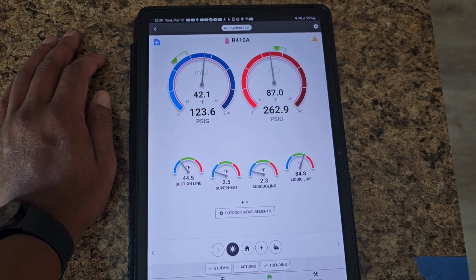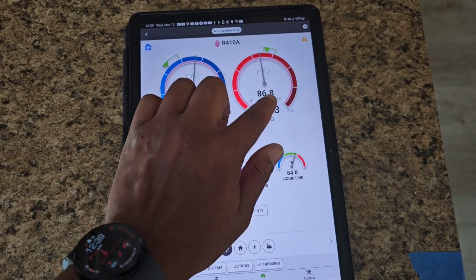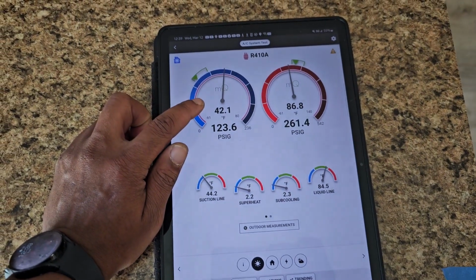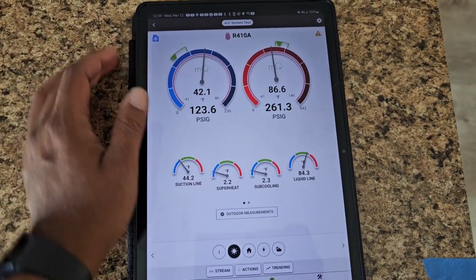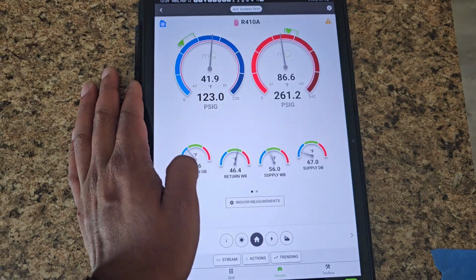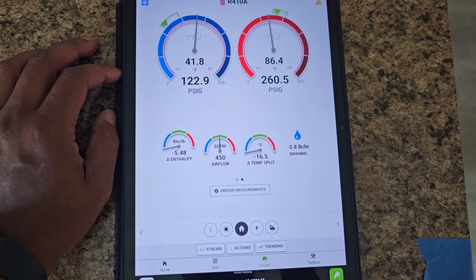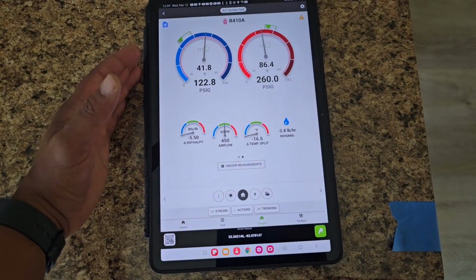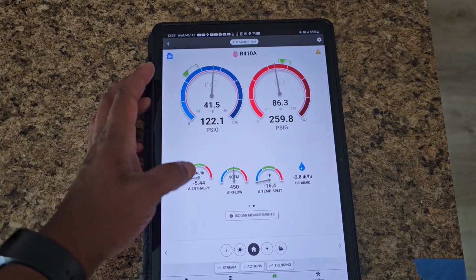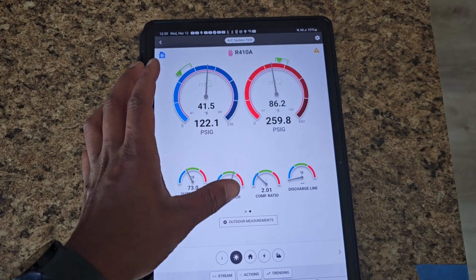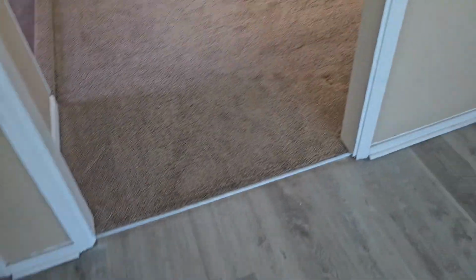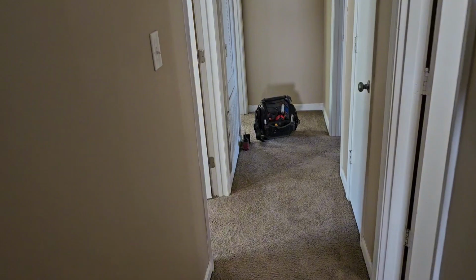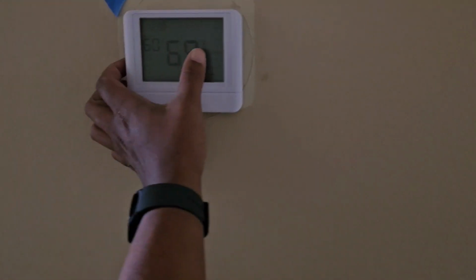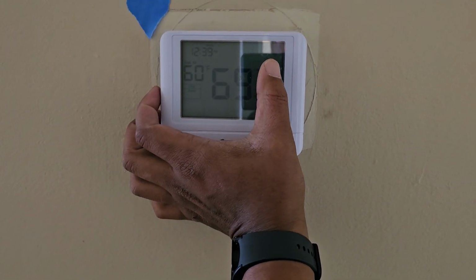I'm working with a 2.5 ton condenser and a 3 ton evap coil with a TXV. So honestly, my boss would tell me to just leave it and see what goes on in the summertime because of the temp split. So that's what I'm going to do. But you guys let me know in the comments how you would go further about diagnosing this potential issue. I'm still going to take the blower motor panel off and measure this back panel and see just how low we are on... oh snap, let me screenshot Delta T's real quick for the invoice.